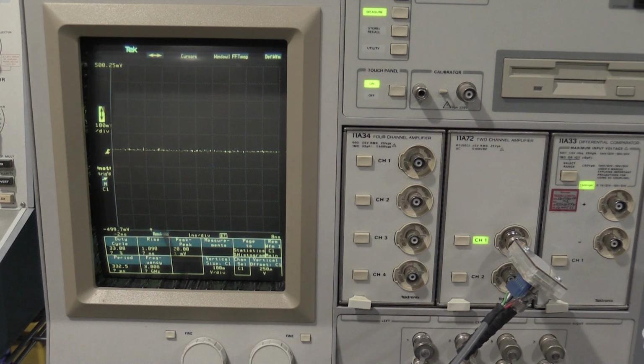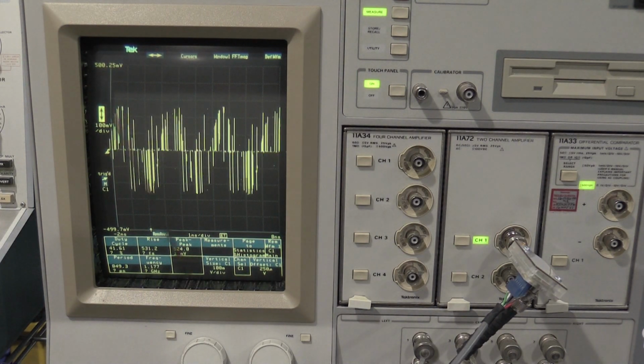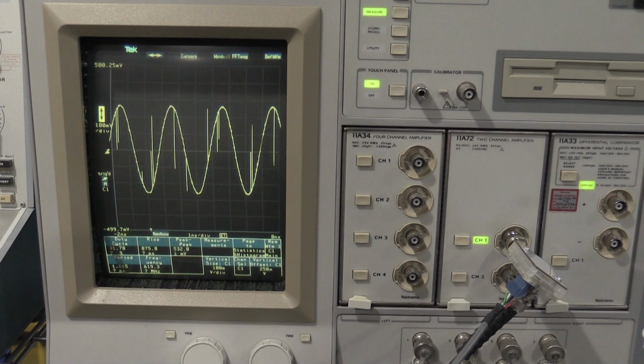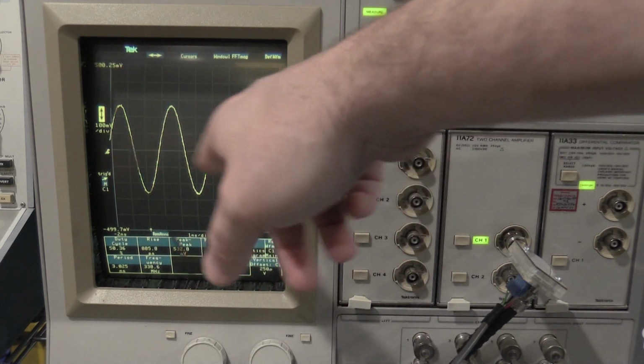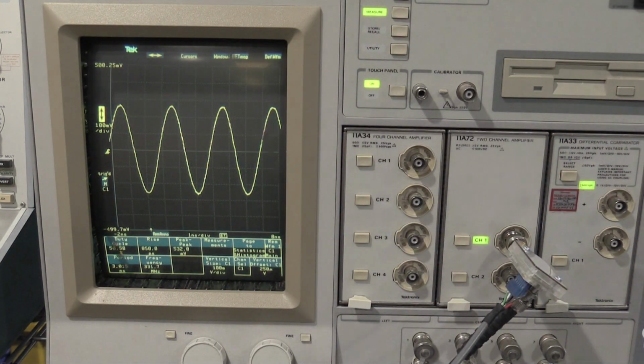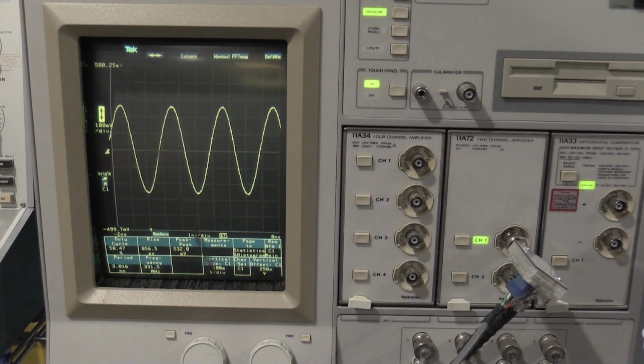So I have it set up on the low range now, about 330 megahertz, all the way down on the amplitude. And we will turn the generator on. And we get some triggering, and there we go. The noise you saw in the trace here was just the DSA building the waveform and doing the sampling, so that is expected behavior. 327 megahertz, and we have half a volt peak to peak, which is exactly what I have it set to on the front end. So low range works. See what happens when we kick it into the high range.